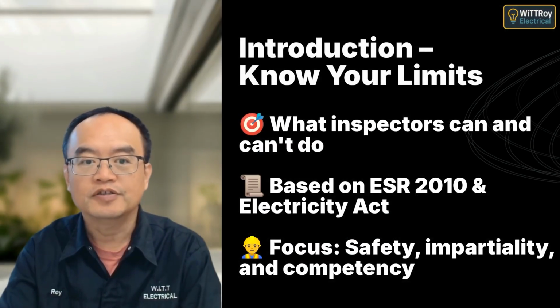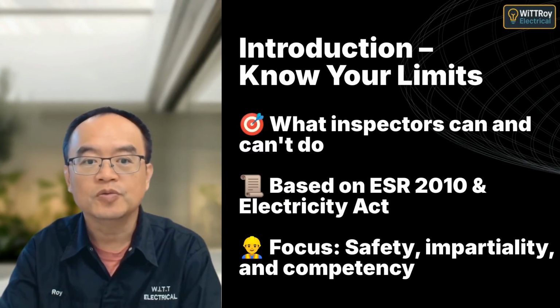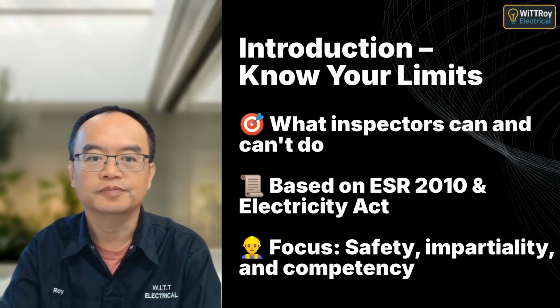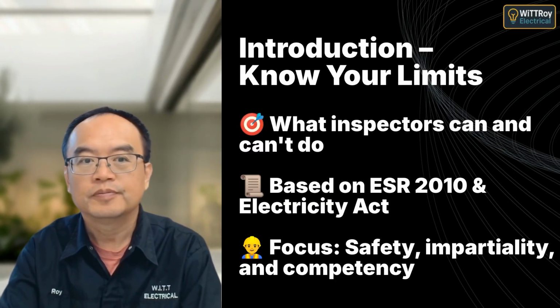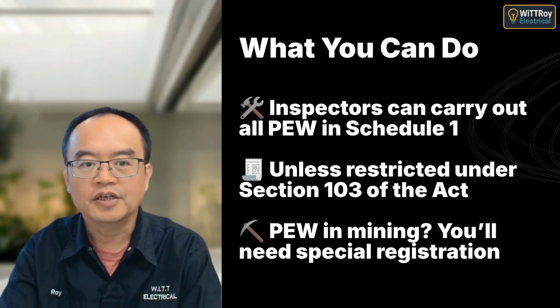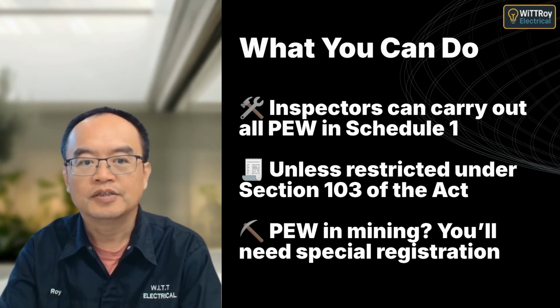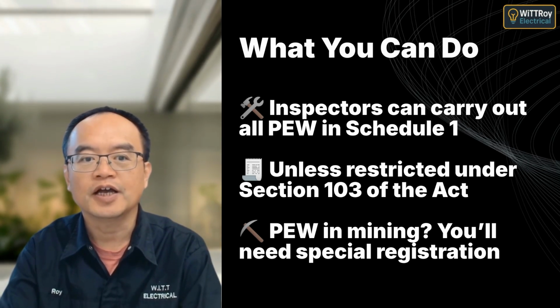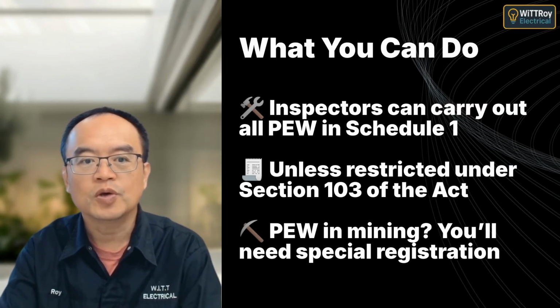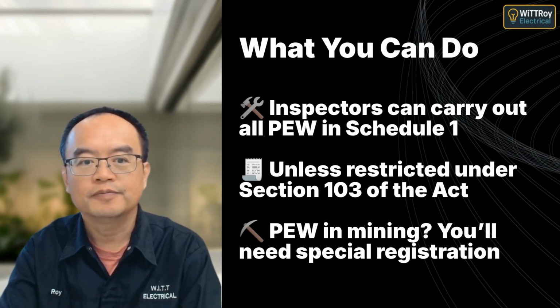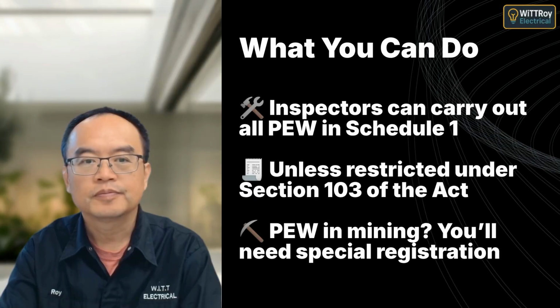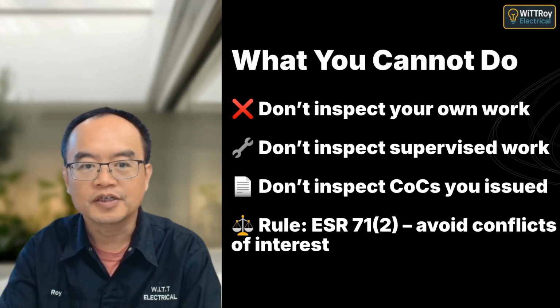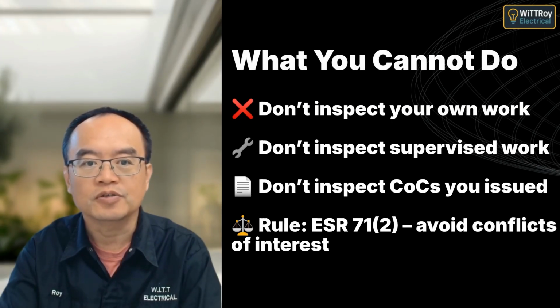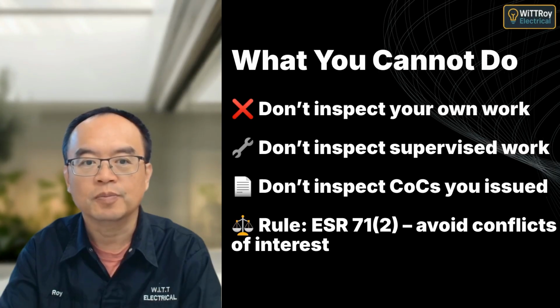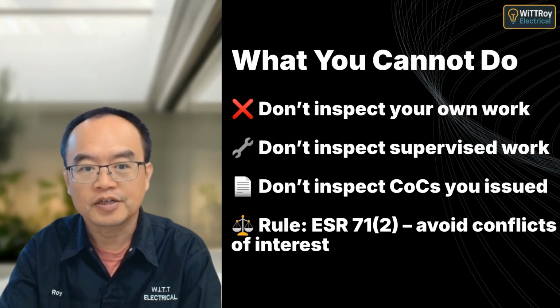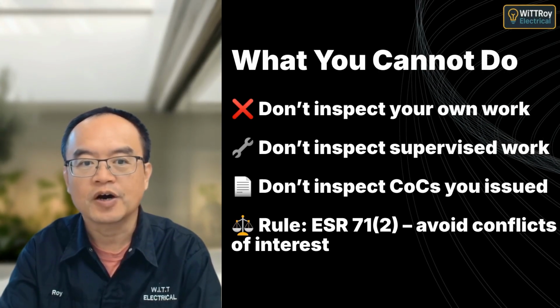Here's a quick breakdown of Section 10.1.1, Limits of Work for Electrical Inspectors. First, inspectors can carry out all prescribed electrical work listed in Schedule 1 of the ESR, unless restricted by the board under Section 103 of the Electricity Act. Second, inspectors must not inspect work they did themselves, supervised, or issued the Certificate of Compliance for. That's straight from ESR 71.2 to prevent any conflict of interest.